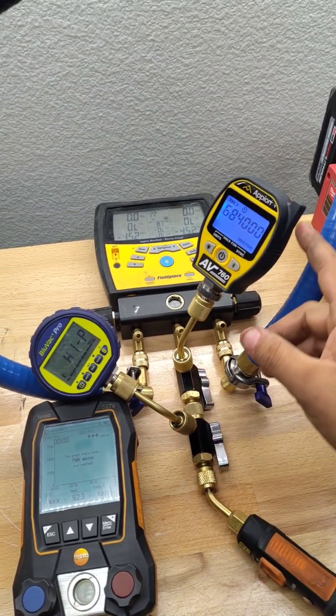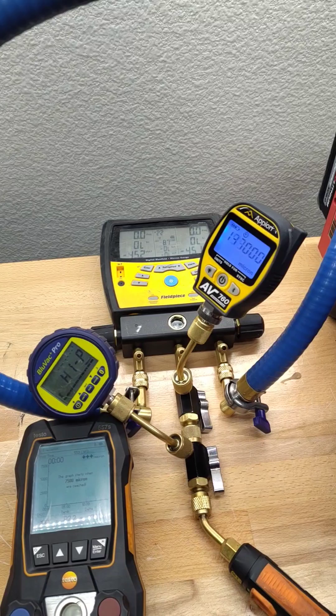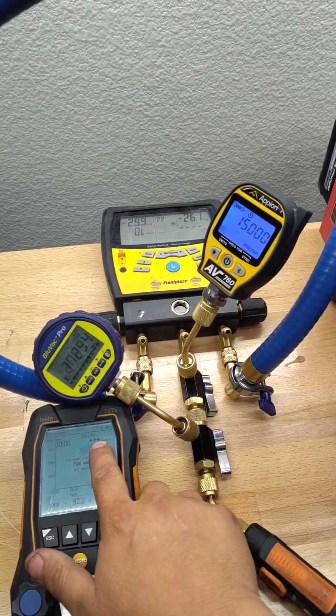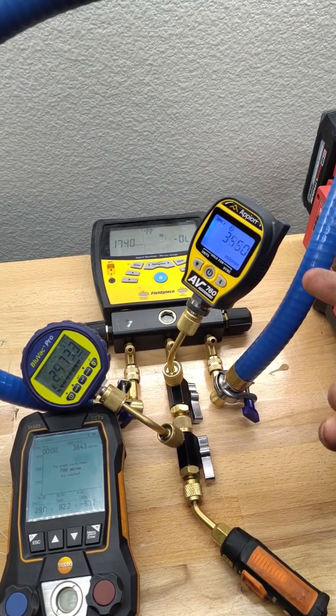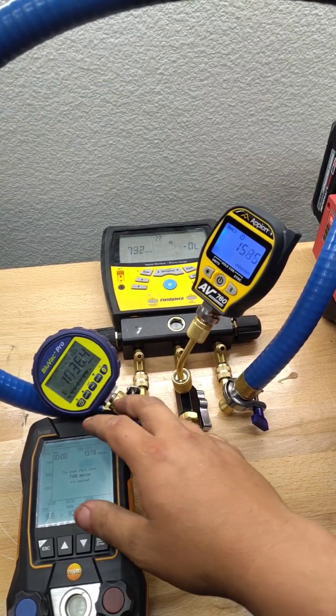Anybody else notice this with Appion gauges? If I turn on the vacuum here, the Testo is going to read right here, and then you've got the BluVac and the Field Piece — and the Appion always seems to read about double. It's just not in the range of these other three.